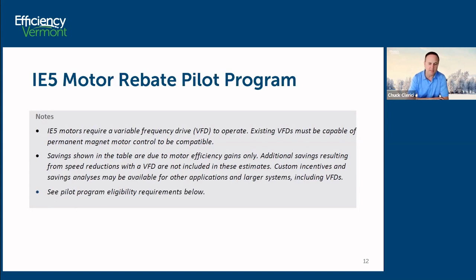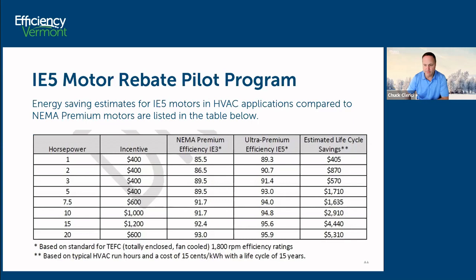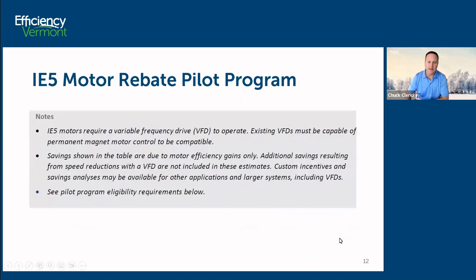And as time goes on, we will see tables come out where IE5 motors are proven to be compatible with drives from Danfoss and Westinghouse and all the prevailing drive manufacturers. The table I just showed a minute ago, I'll flash back to it for a moment. The savings on the right side here is predicated on full load efficiency operations.